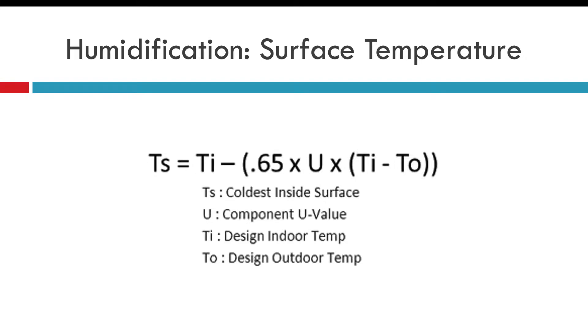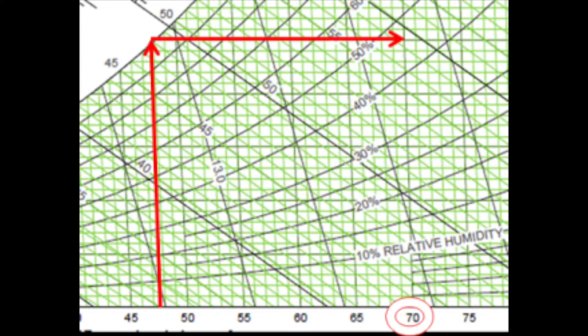Here's the equation. You need to know the component U value — in this case the window — the design indoor temperature of 70 degrees, and the design outdoor temperature of zero. Do the math within parentheses first: temperature inside minus temperature outside. Then multiply the constant of 0.65 by the U value by that temperature difference, and subtract the result from your design indoor temperature. That gives you the coldest inside surface temperature. When you run the numbers, the surface temperature of the window at design conditions is 48 degrees. Cross-referencing 48°F on the psychrometric chart, the maximum relative humidity before reaching the dew point of the air is 45%.